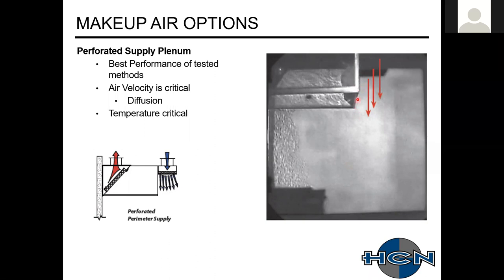These are hung 80 inches off the floor. So if your cook's about 6'1", 6'2", they should feel the air on their head, but not blowing hard down, just a nice laminar flow. The reason for this is that with the perforated supply plenums, you have multiple perforation layers. The first one slows the air down. The next one distributes it, so you have a nice even laminar flow of air.